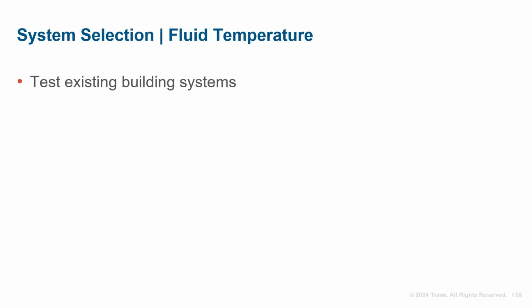Thanks, Sarah. Once all the building survey work is complete and the load profile is known, the analysis can begin to determine the optimal hot water supply temperature. As Sarah went over a few minutes ago, lower hot water supply temperatures improve unit capacity, efficiency, and selection options. The lower the hot water supply temperature, the better.